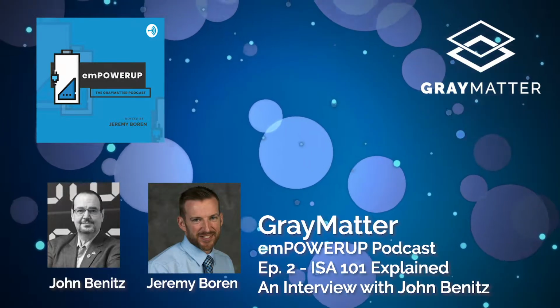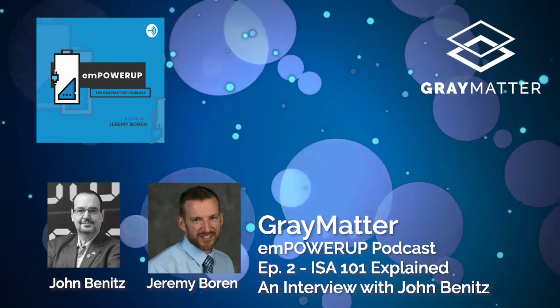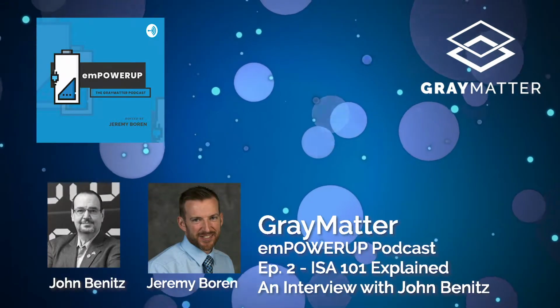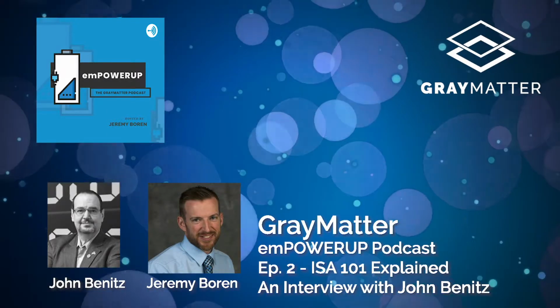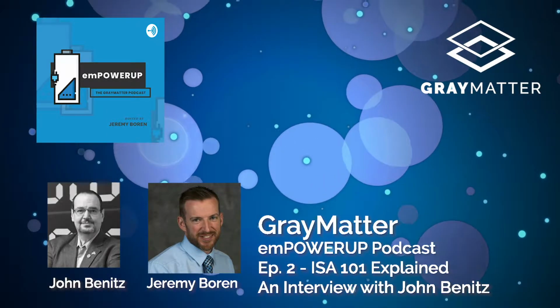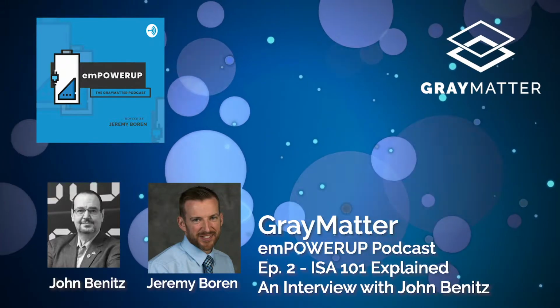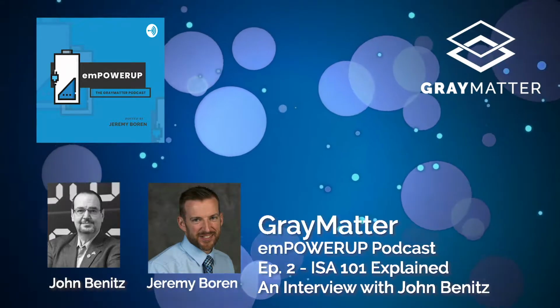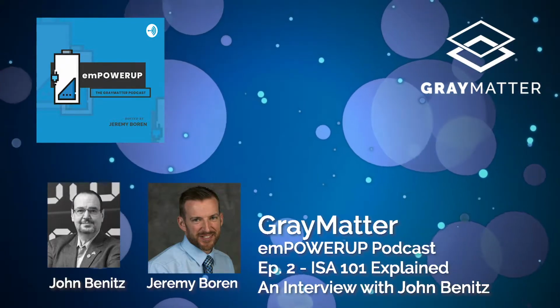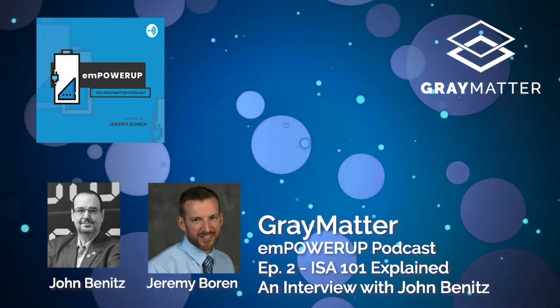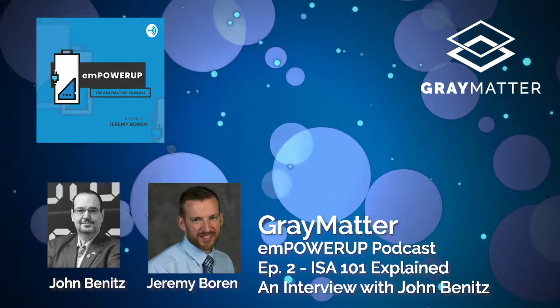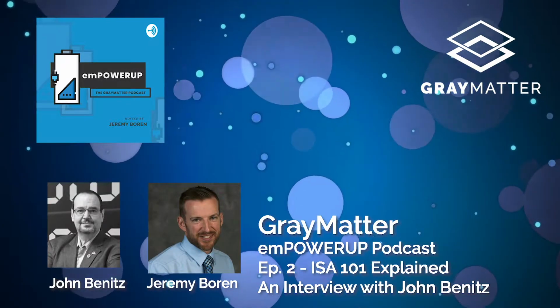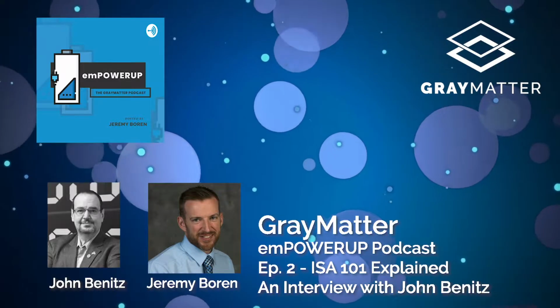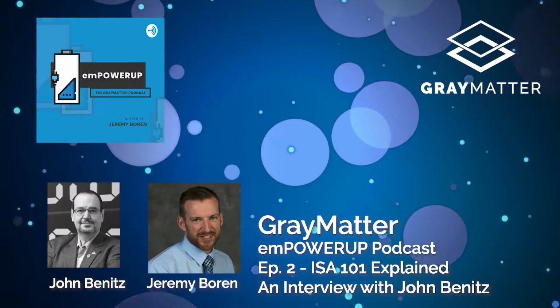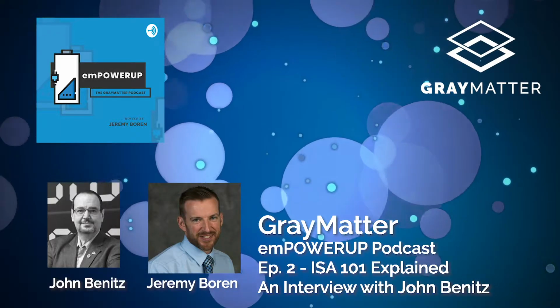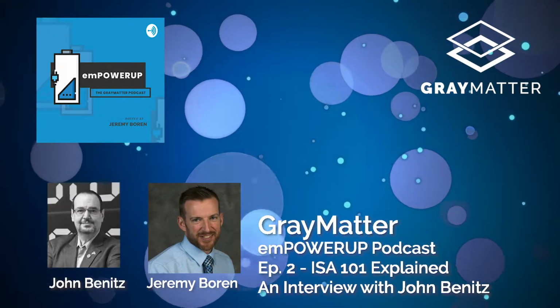And then from there, we had to start talking about, well, how do you develop this graphic? What needs to be on it? What are the different areas? We talked about the different colors. Well, what was color really going to be used for? Color is used to draw your attention. It's either to draw your attention to a state, or it's to draw your attention to an action that needs to be taken. Well, a lot of people are using red and green to determine states. So a lot of people on the standard wanted to dictate what that meant.